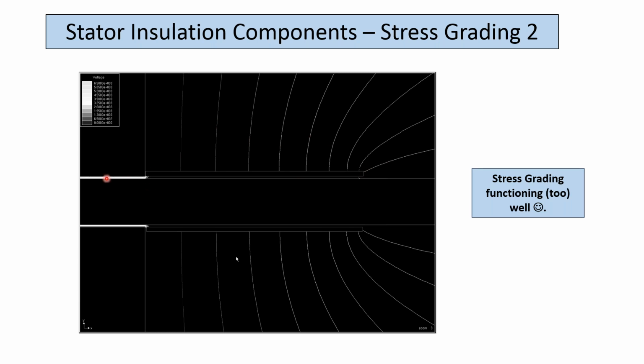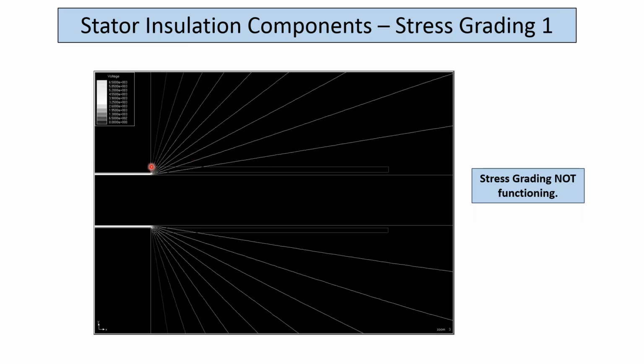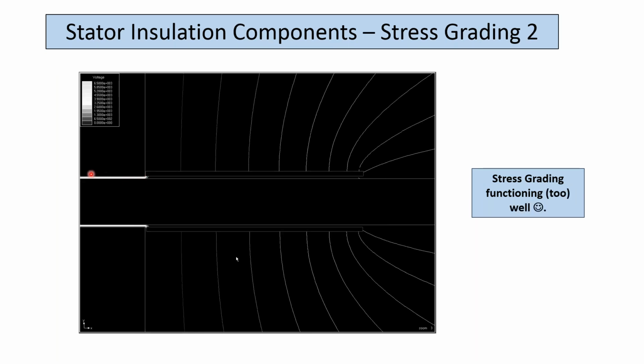So it does nothing to the electric field inside the slot. It stays just as high. But look how high that electric field is, even with or without decent stress grading. So you would have gradual wear occurring due to the corona discharge on the overhang, but you still have no failure inside the slot. And it's a tremendously high electric field, and it's why the main insulation thickness is so important on these machines.